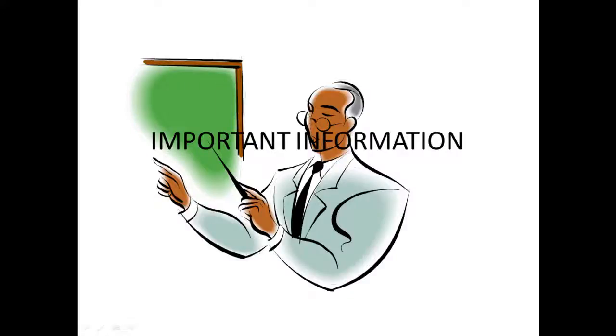Okay, with Class 2, there's one extra thing I need you to do. You need to do it with Class 1 as well, but it's not as critical. You need to talk me through how you identified the equipment as Class 2. You need to go through the stages of finding the double square marking or double insulated written on it somewhere. If it isn't, I need you to explain to me how you identified it as Class 2 without the marking.